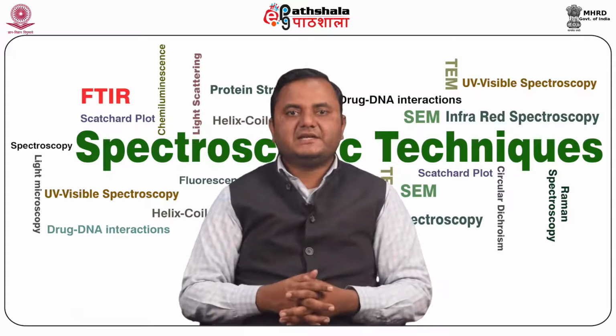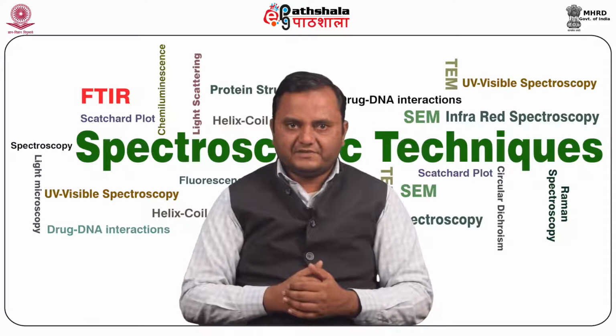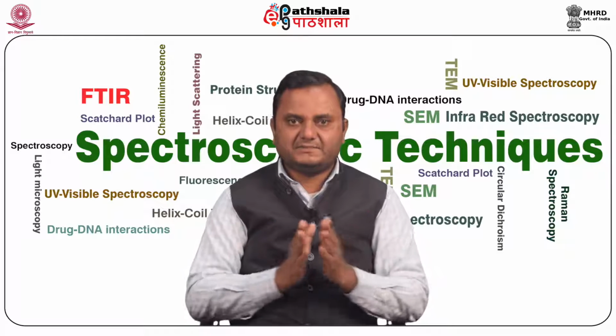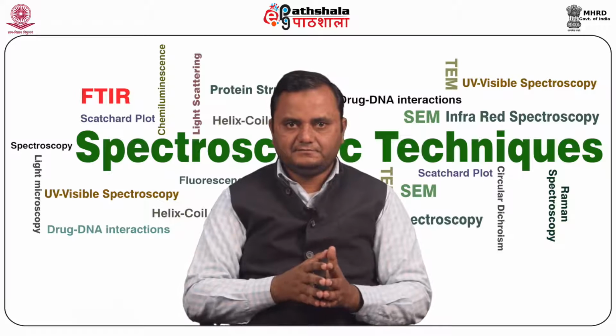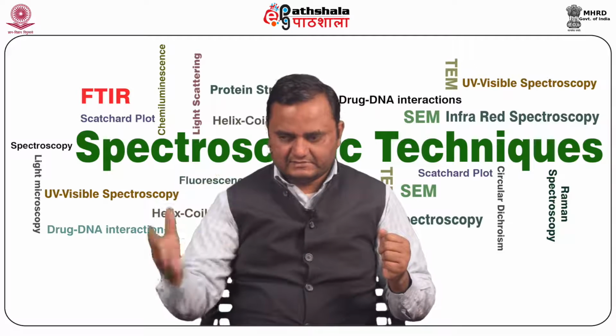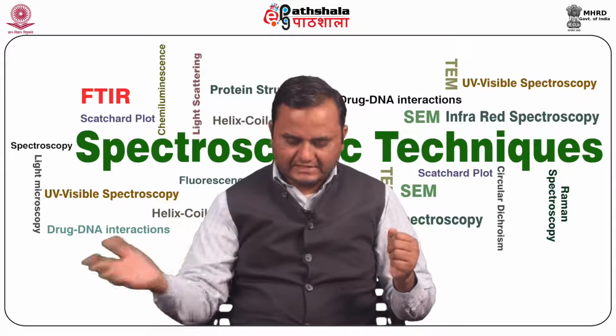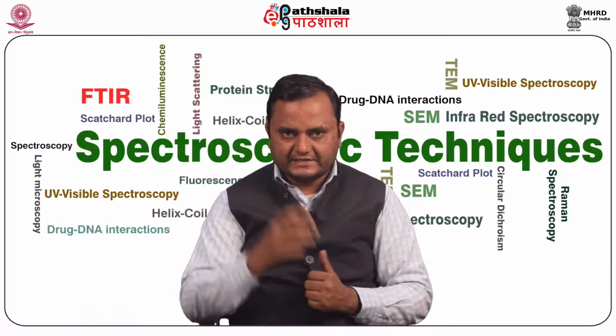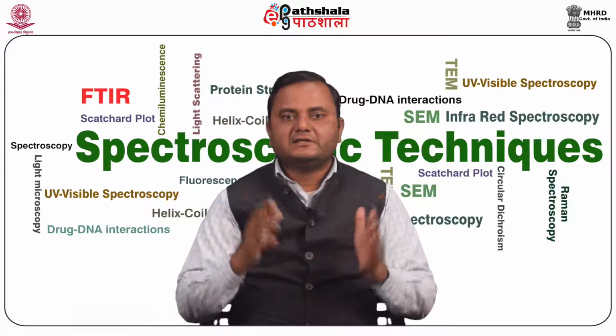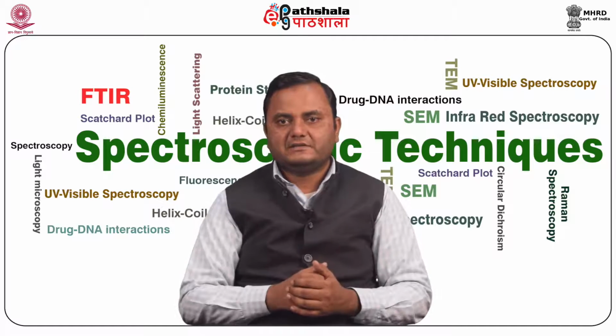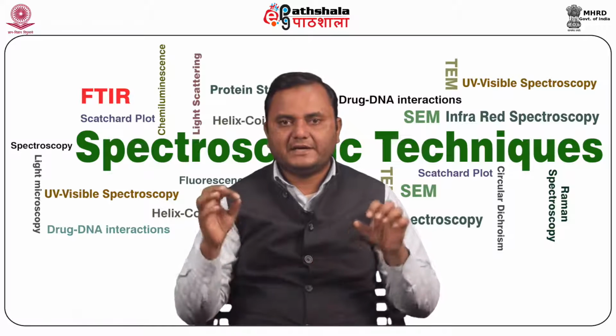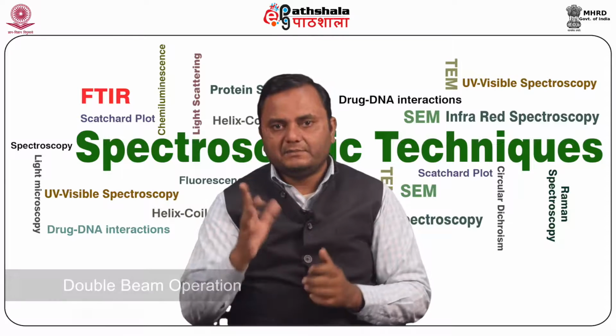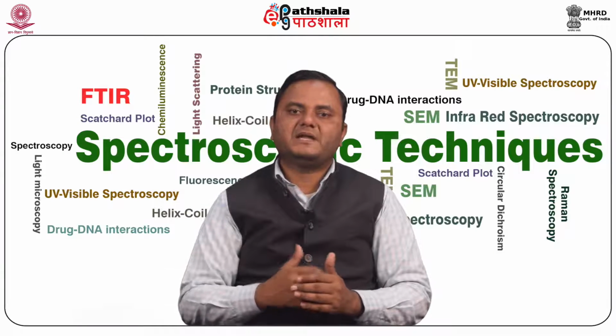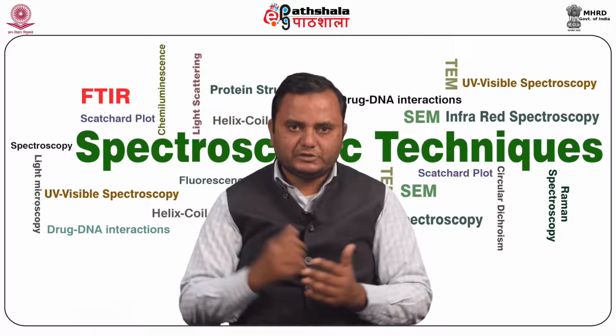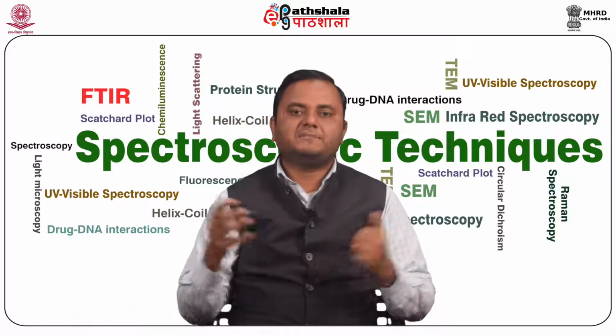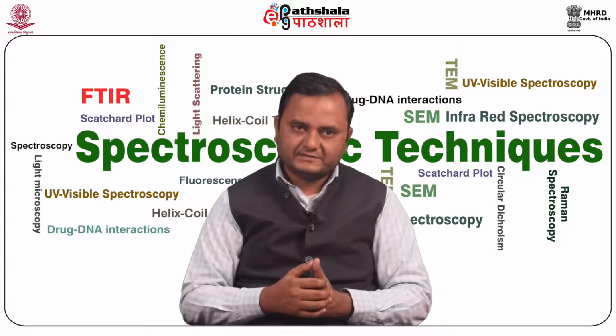The source generates light across the spectrum of interest, and a monochromator separates the source radiation into the different wavelengths required by the sample. Then it selects the collection of wavelengths that shines through the sample at a given time. In double-beam operation, the beam splitter separates the incident beam into two halves, one going to the sample and one to the reference.